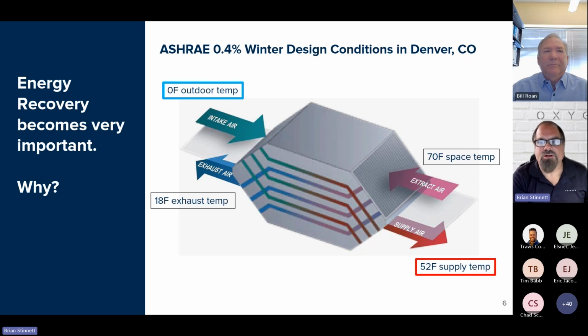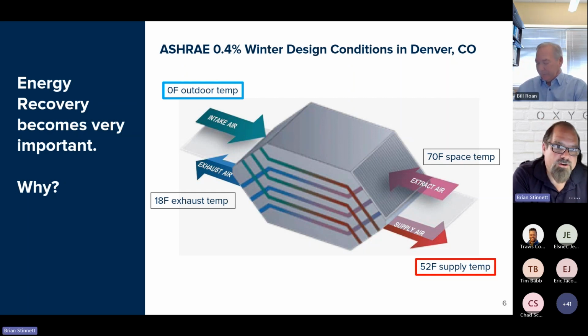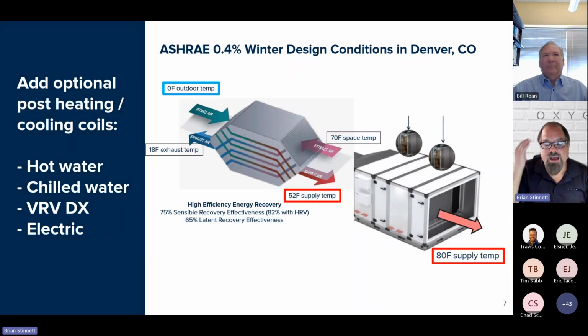Now, why is energy recovery so important? If you take a look at the graphic on the slide, you can see that 0 degree air in Denver is going to be heated up with the exhaust air to 52 degrees. Let that sink in a minute. We're going to take that heat out of the exhaust air that we would normally be blowing outdoors, and we're going to transfer 70% or more of that heat to the incoming outside air. As shown here, we're going to do it with a stationary plate heat exchanger. No belts, motors, seals, etc. Zero cross-contamination in a plate heat exchanger, and we're going to pick up a 52 degree delta T on that incoming outside air. So once we've done that, now we've got 52 degree air.